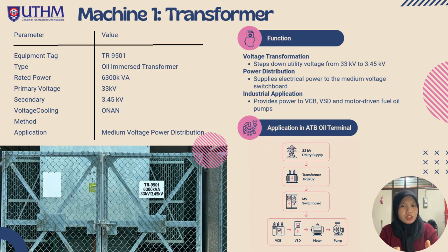The main function of the transformer is to step down the incoming utility voltage from the 33 kV to the 3.45 kV. It also provides electrical isolation between the transmission network and the plant electrical system. In addition, it serves as the main power distribution source for downstream electrical equipment.